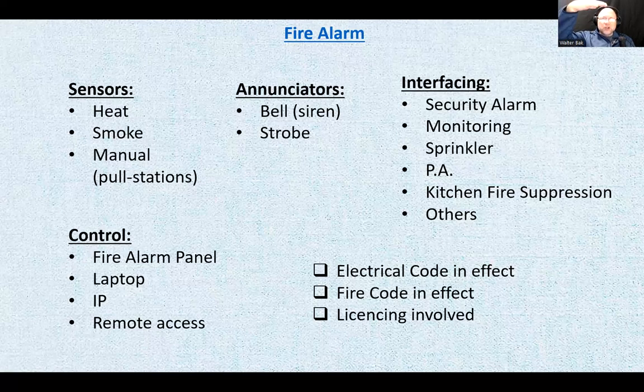Kitchen fire suppressions, this is almost like a topic on its own. This would be the hoods over the gas stoves or wherever the gas heat and flame is, and sometimes they're mandatory to install. It's a whole system that has heat sensors on top at the hood, and if the heat gets too much, the sensor reacts. Basically it's like a line that can be burned through, and it opens and manually triggers the fire suppression system, so it sends a signal to the fire alarm. It also triggers an extinguisher, a huge fire extinguisher that's going to extinguish the fire and then pour water on it so the fire doesn't restart, just to cool down the heating elements. It's almost like a science of its own.